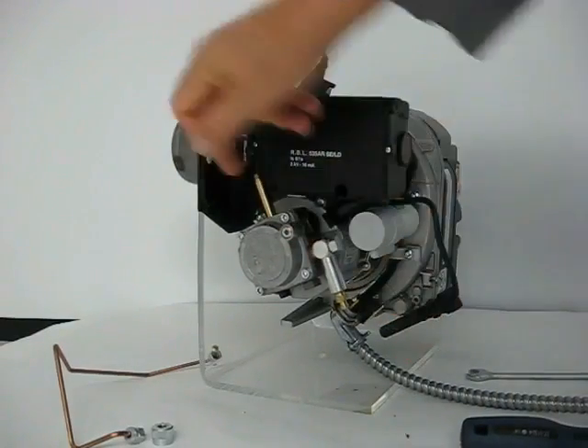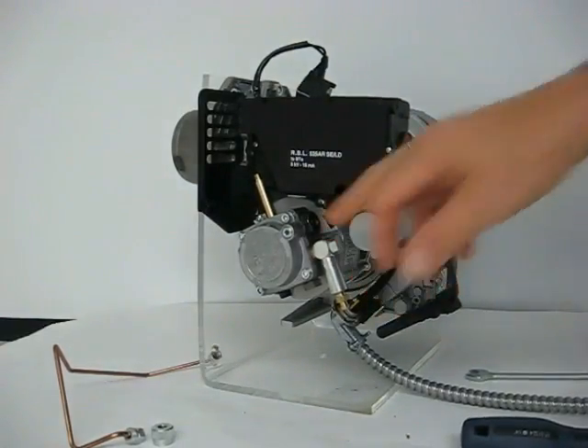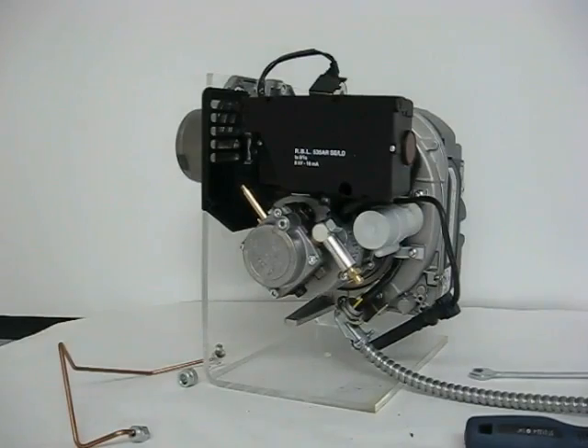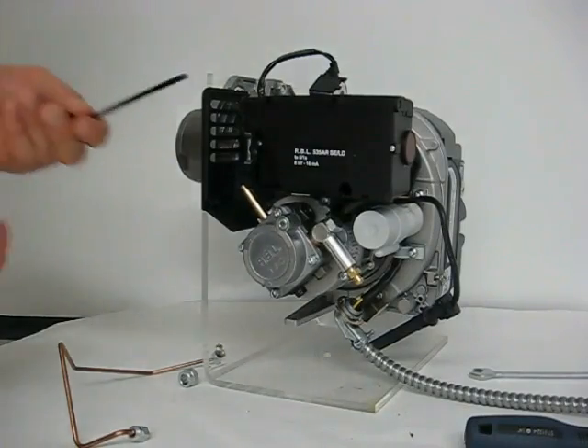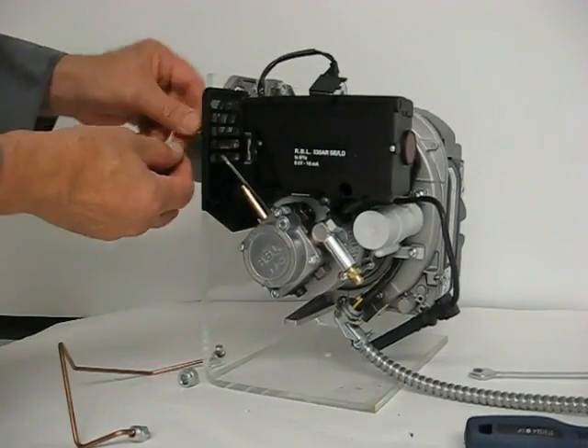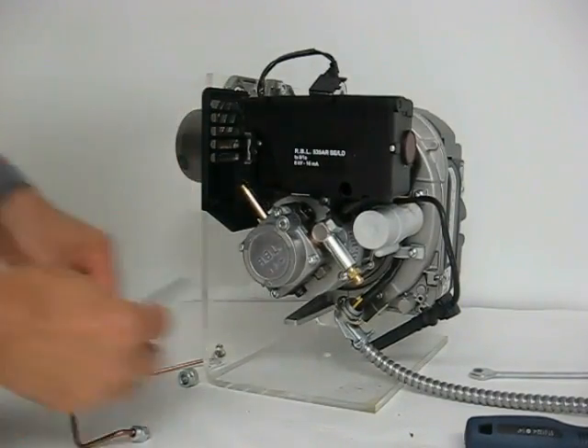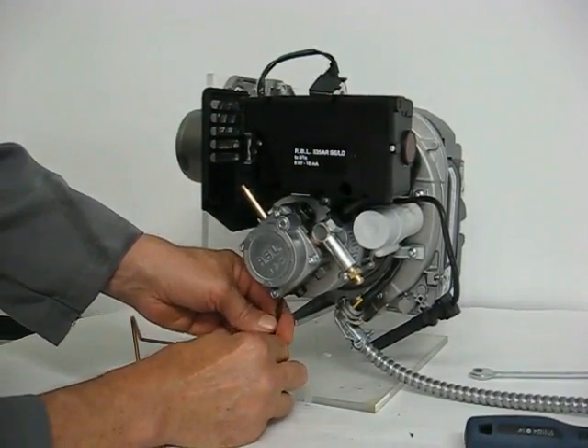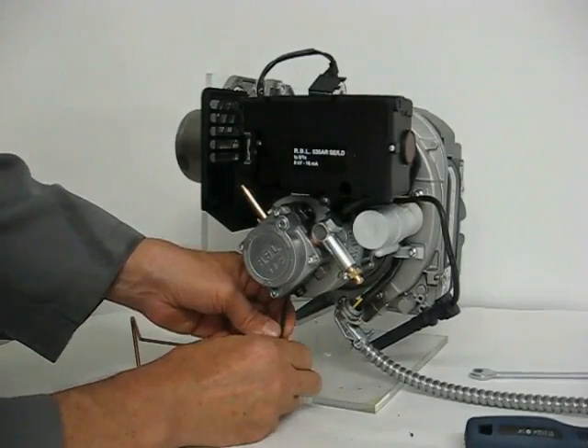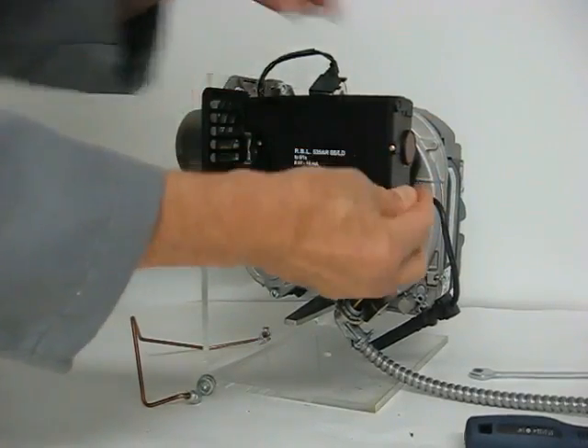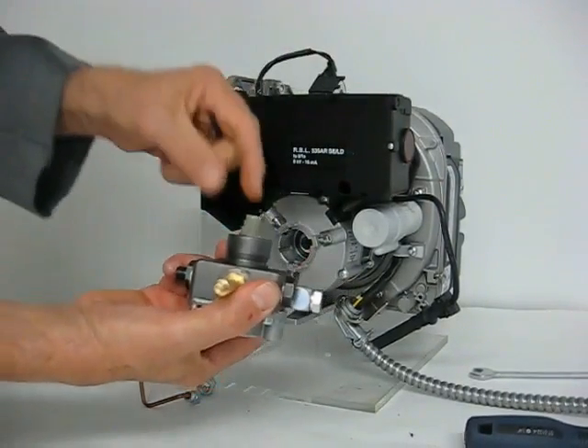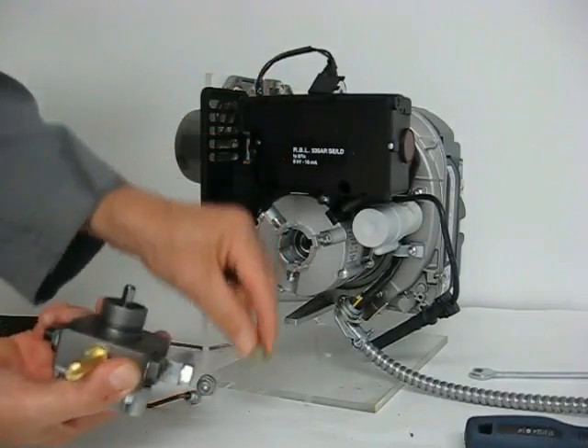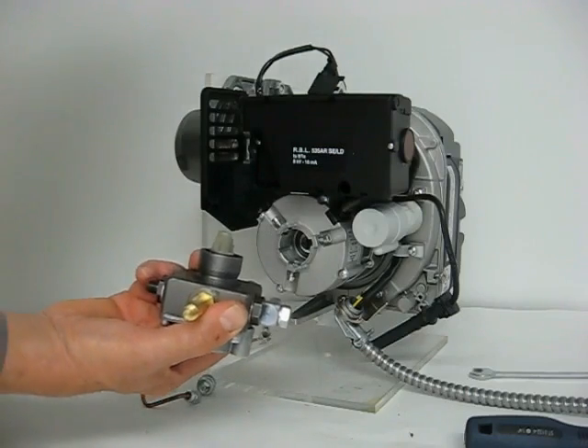There's three allen screws holding the pump to the motor. We have to loosen those screws. You might want to remove this air cowl here for ease of access, but if your allen wrench is long enough, you can just slide it through. Loosen the screw on this side of the pump, allen screw underneath the pump, one behind the capacitor. And the pump will slide off. Don't lose the coupling. The coupling is the connection between the motor and the pump. Without that, the motor won't drive the pump.